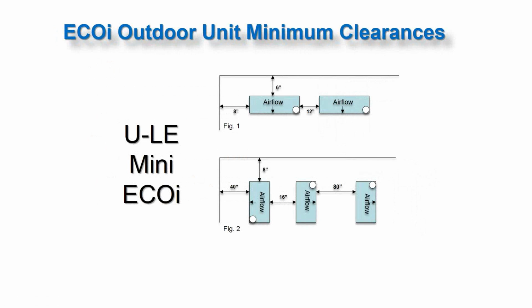Okay, U-LE Mini ECOi condensers are the first offering. This is the single phase unit, 36,000 or 52,000 BTUs. This is the clearances, minimum clearances for our unit. So when we have air discharging out the side this way, away from a wall, this is an L-shaped wall here. We have 8 inches from the side of the unit, and then we have 6 inches clearance from the coil side. This would be the coil side, this would be the fan side. Okay, and then if we want to put units next to each other, we need 12 inches, a foot minimum, between units.